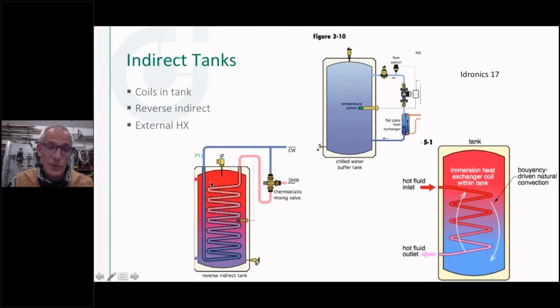You can use that as both your indirect heat source as well as your buffer tank for maybe a microzone system. And this is a nice way to do it, in that you can just buy a blank tank. You could just buy an inexpensive electric water heater, just a plain steel insulated tank, and then put the heat exchanger on the outside of it. Now it's going to cost you a circulator pump to do that, but the nice thing about that is you can size that to exactly what the load is. If it's doing a domestic water load, or it's doing a radiant heat load, you size the plate heat exchanger and the size of the circulator.